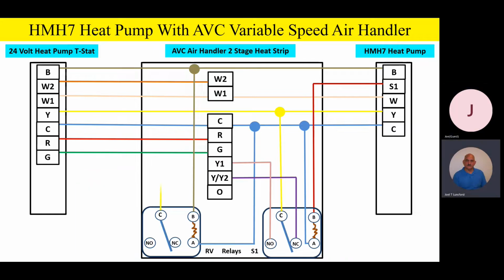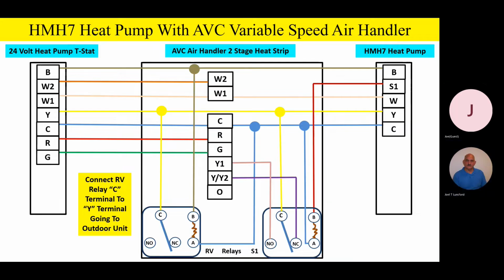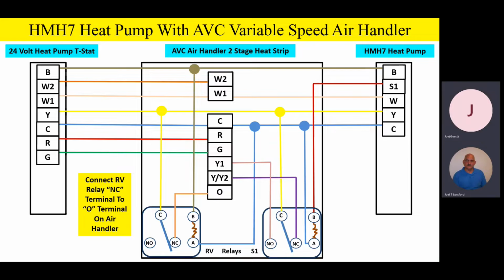Now, how this works is this: the C terminal on the RV relay, the common terminal for the switching contacts, goes up and ties on to Y, just like we had on the other relay, right? So the compressor's running. We have 24 volts on that C terminal. Now watch this. The normally closed contacts on that RV relay go over to the O terminal on the variable speed product. Now, this is real important.